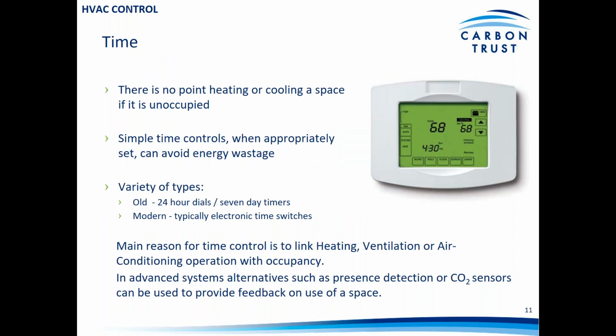Another important factor is controls, is time controls. So there's no point heating or cooling a space if it's unoccupied. For a business with basic needs, you may operate fixed hours, 9 to 5, Monday to Friday. So ensuring that you have good time controls, that the building is warm enough at the start of the working day and that the heating is switched off at the end of the day, may well provide the level of control needed for your business.